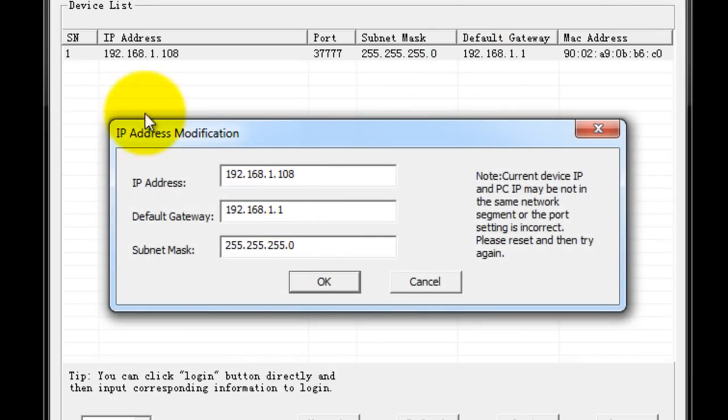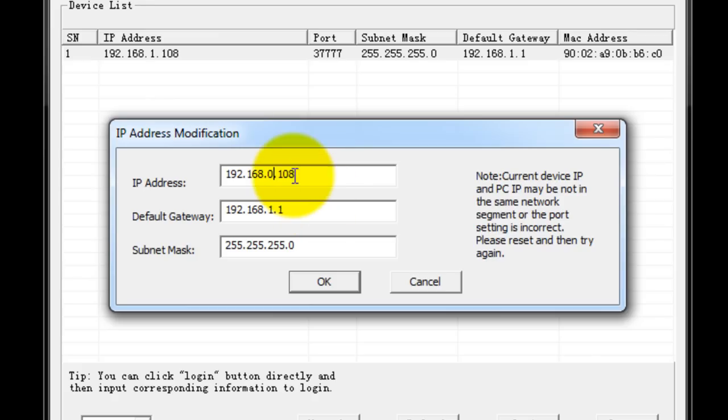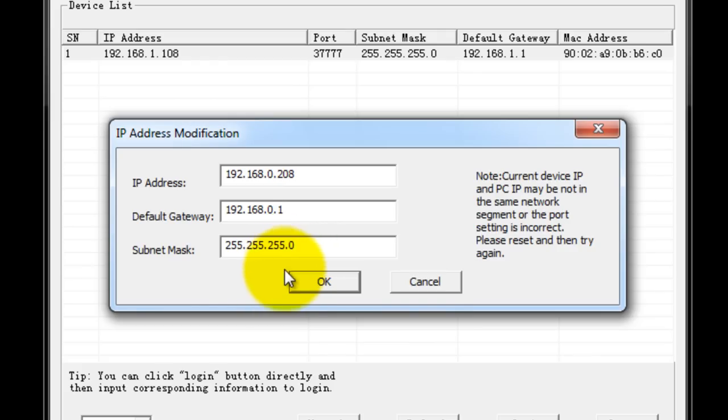As you can see, I got the IP address modification came up. So I'm going to change this to a zero and give a number that's out of range, like around 200, and change the default gateway to the same default gateway for my main switch. And I'm going to click OK.